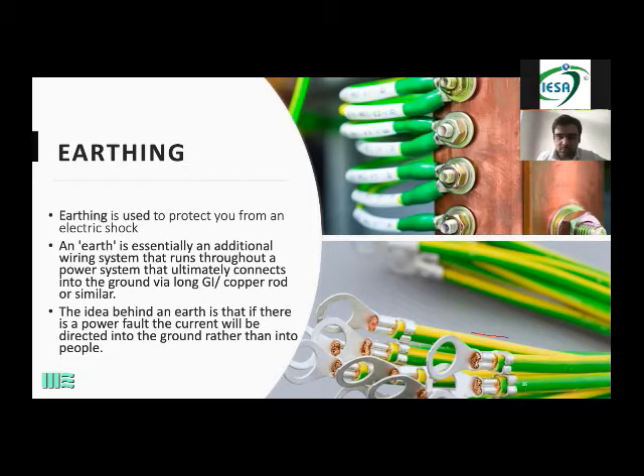When you're using loose wire, when you're dealing with the pliers, when you're trying to tighten the wires, if these strands break, so this is a 4 square mm wire, maybe a few strands break, maybe it can become a 3 square mm wire. You're thinking that you're providing power up to 4 kilowatts from a 4 square mm wire, but when you're doing those loose connections on site, when these strands break, it becomes a 3.3 square mm wire. So ultimately, when the wire comes, these lugs need to be there.